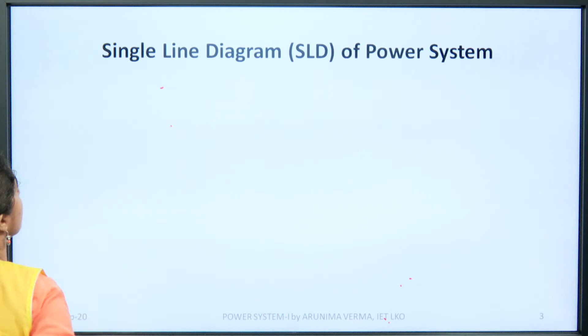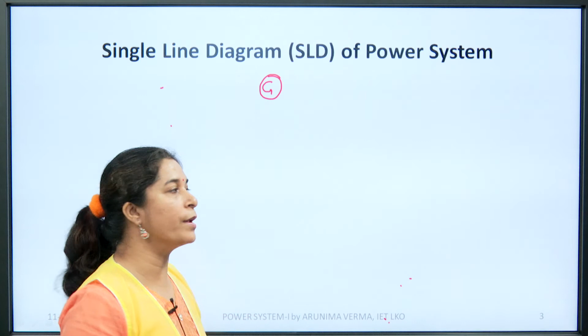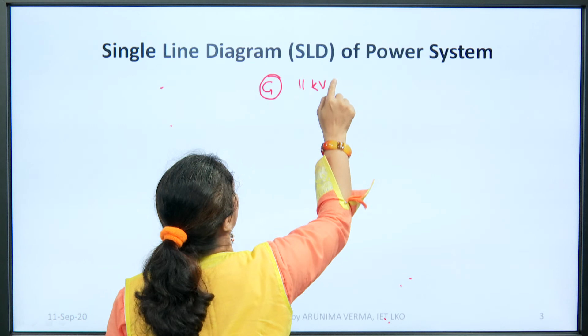Now, as an electrical engineer, I would like to tell you that generation does not take place at very high voltage level, because generators are rated and designed and sized accordingly. So, normally the generation in India, if we specifically talk about, takes place around 11 kV or 33 kV. Now, this is an estimated form of 11 kV or 33 kV generation.